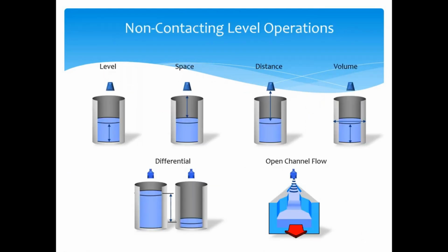Some of the most common non-contacting level operations that you'll see, I think hands down the most common is going to be level. You might also see distance, which we've already talked about, from the face of the transducer down to liquid level. This is particularly beneficial when you're setting an instrument up. It might be much easier to put it in distance mode. Simply put a tape measure down into the vessel and make sure it's measuring the correct distance away from your liquid level. You can also use them for a volume calculation. If you know the dimensions of your tank, we take level, use a formula depending upon the shape of your tank, and give you a volume output.